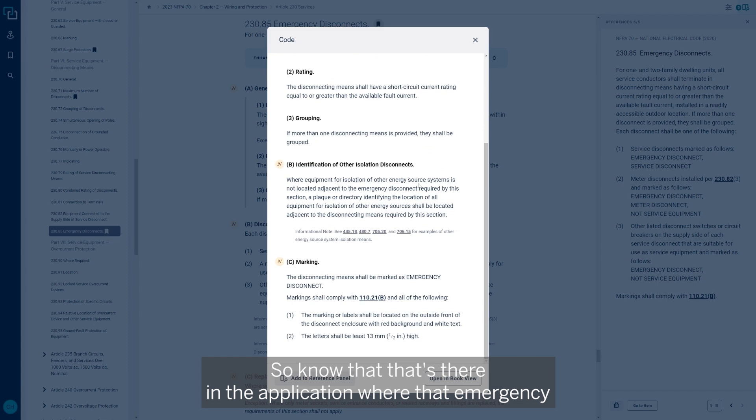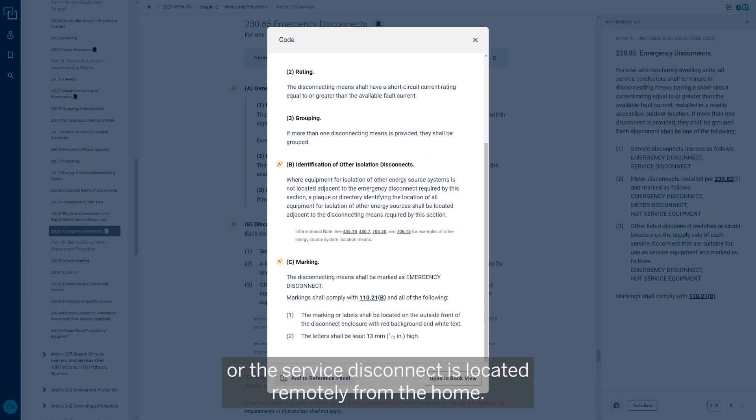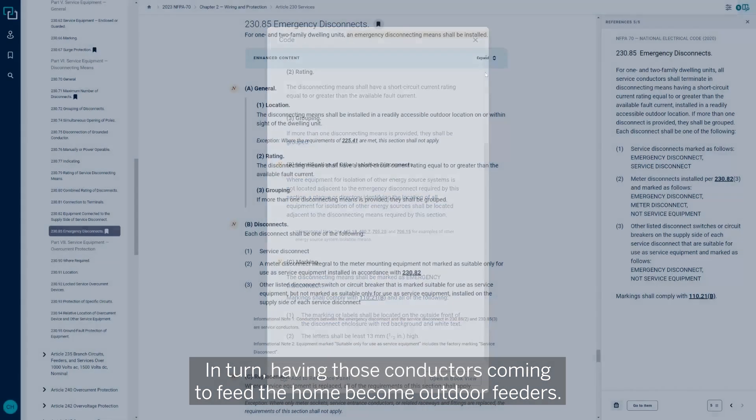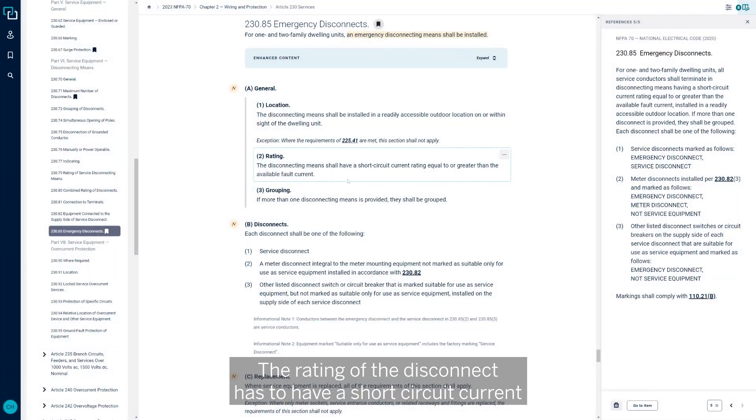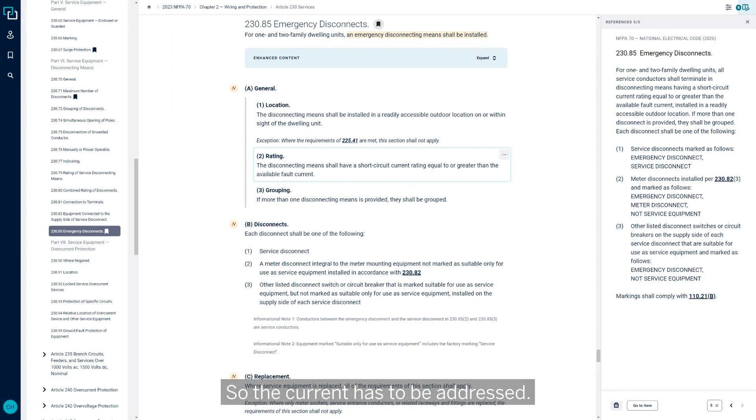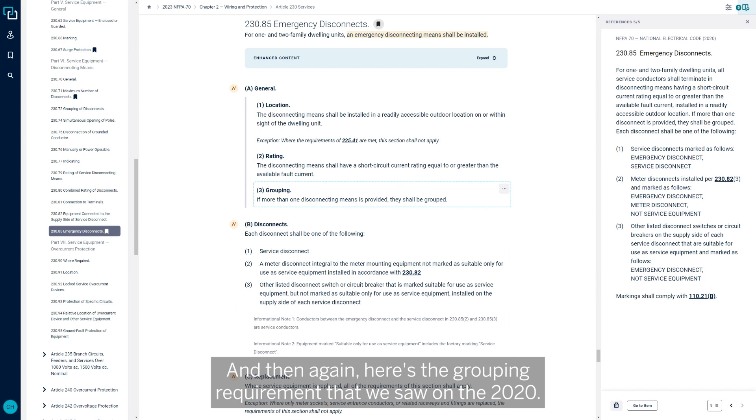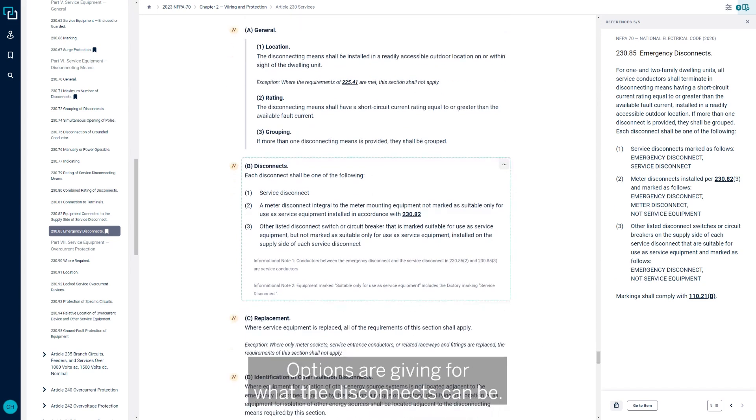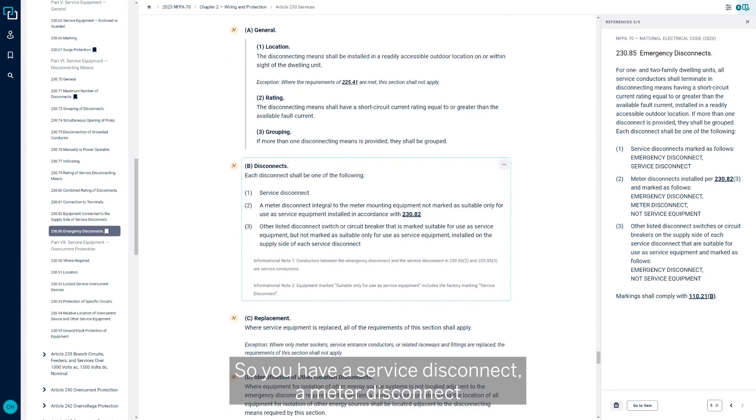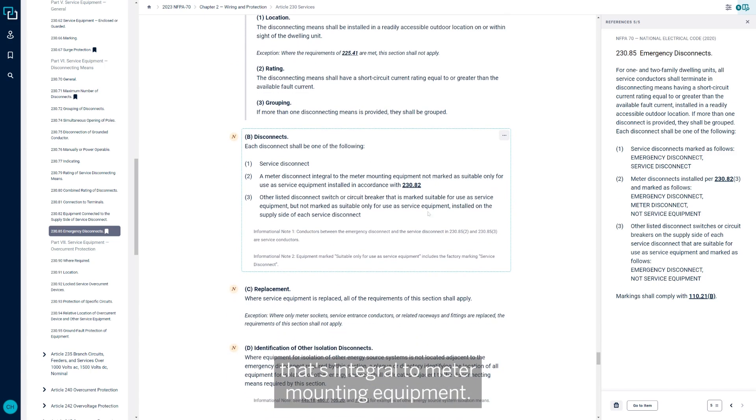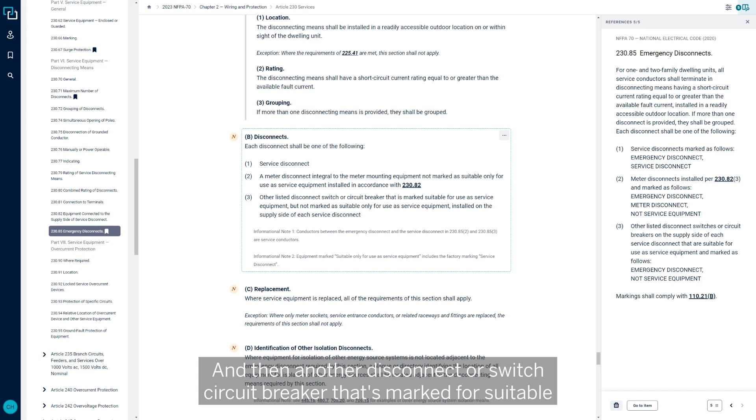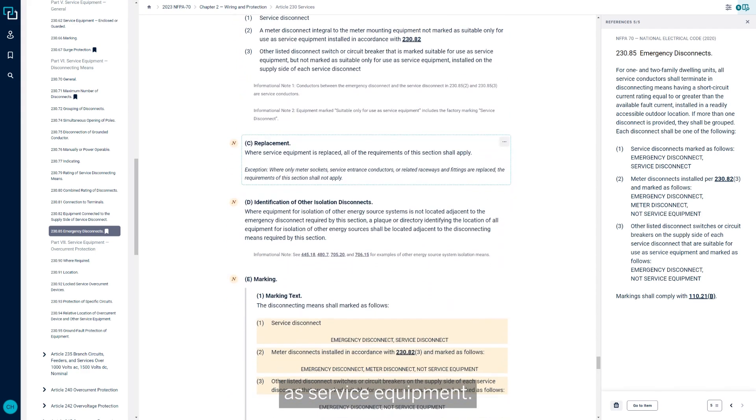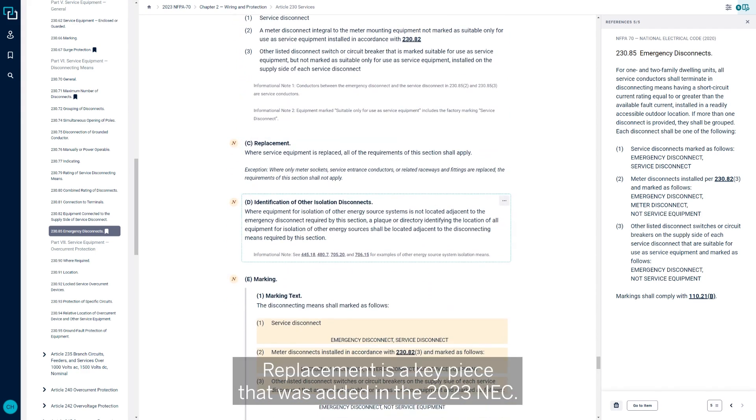In that case, those conductors that would feed the home would become outdoor feeders, which would be covered under Article 225. So there's an exception here that says where the requirements of 225.41 are met, this section does not apply. It's essentially how the wiring is done to feed the home. The rating of the disconnect has to have a short circuit current rating equal to or greater than the available fault current. And then again, here's the grouping requirement that we saw on the 2020. If one or more disconnecting means is provided, they need to be grouped.